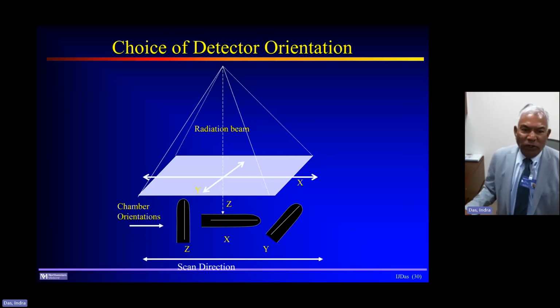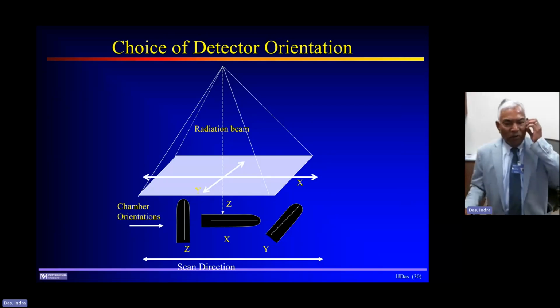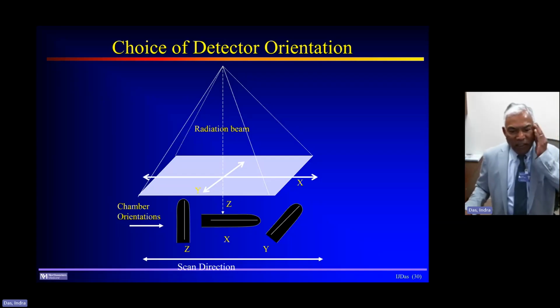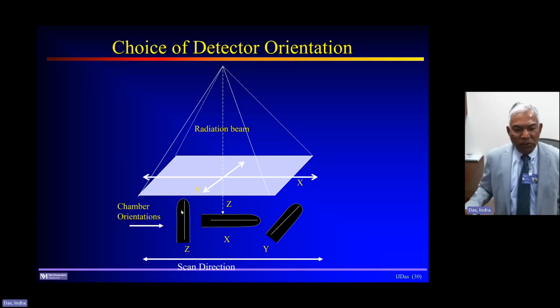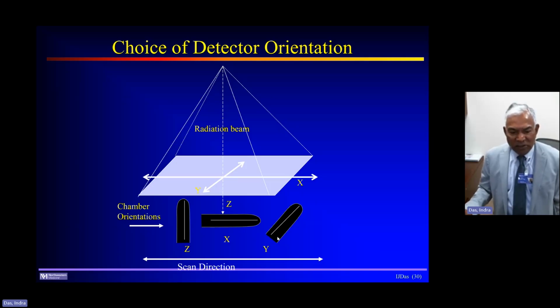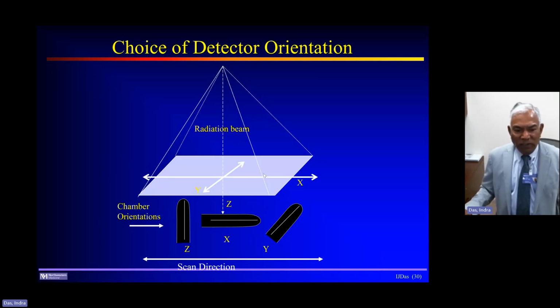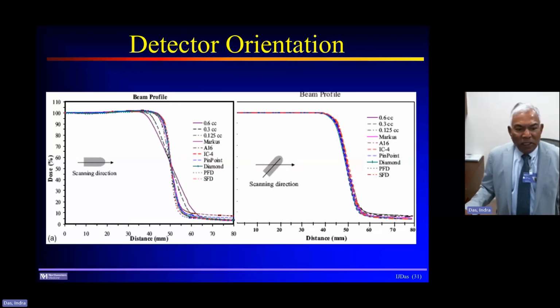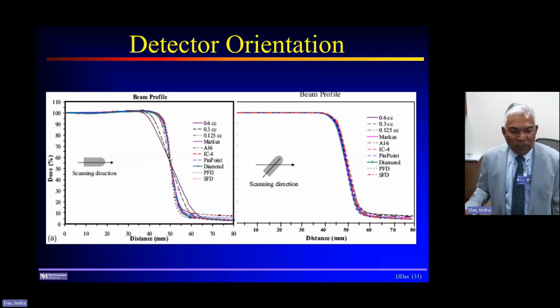The other thing is the choice of your direction, how you are scanning. Obviously, for any detector other than the spherical chambers, there are three orientations: the vertical orientation, the X orientation, and the Y orientation. And one has to pay attention to where you are scanning. Obviously, if it is a very, very small detector, then you don't have to worry about these orientations. But in general, most detectors have a finite size, volume averaging takes place, and then you have to worry about that. These are all from TG106.